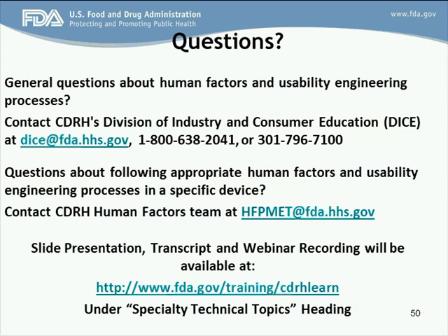We don't mention it in the guidance as such, but that is a tool that's commonly used to enable that work to happen and tie everything together, especially if it's done electronically, to link those things and assist you in the product development effort. But from the regulatory submission standpoint, it may or may not be useful depending on how complex the product is. Those trace matrices can become quite cumbersome. So it's a question of whether it can convey that information or whether it's more of an internal tool. So we don't discuss it in the guidance per se.